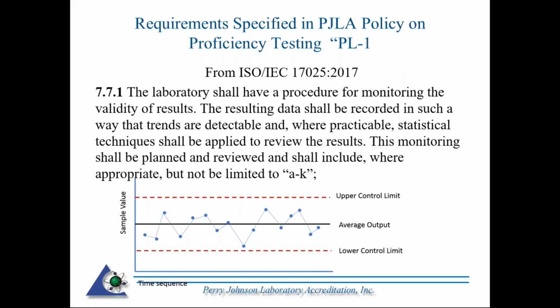I also mentioned that the requirements in 17025 are incorporated into PL1, section 7.7.1. If you think about it, the laboratory shall have a procedure for monitoring the validity of results. The resulting data shall be recorded in such a way that trends are detectable, and where practical, statistical techniques shall be applied to review the results. This monitoring shall be planned and reviewed and shall include, where appropriate but not limited to... The reason I put this slide in here is I'm thinking of some of these great big labs with a lot of sub-disciplines.